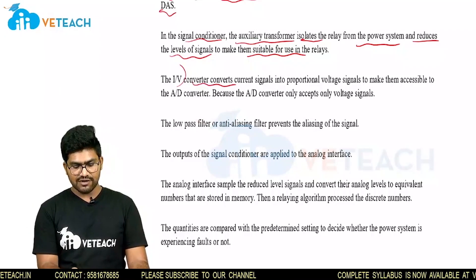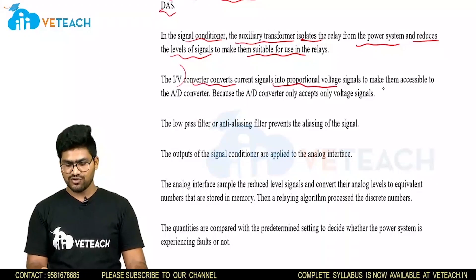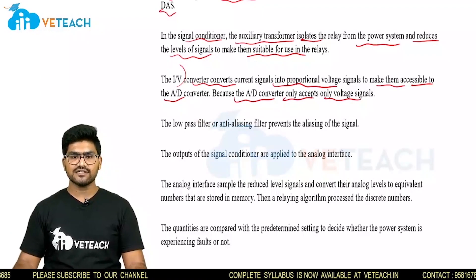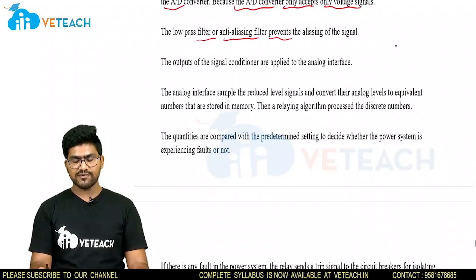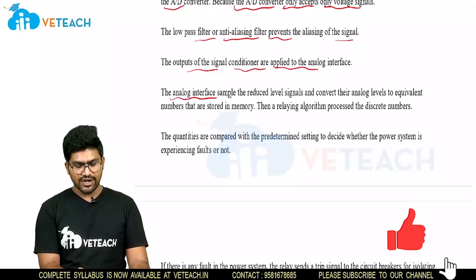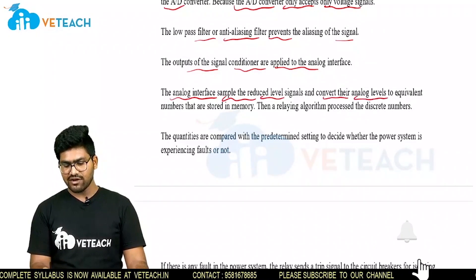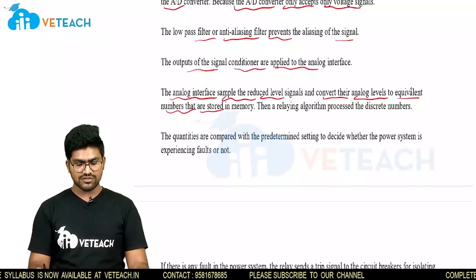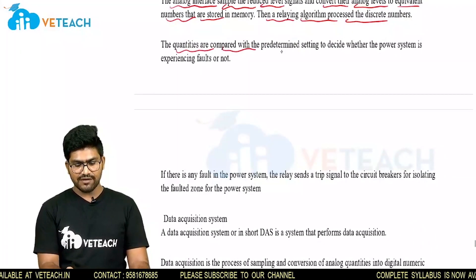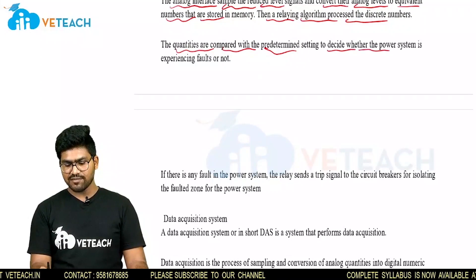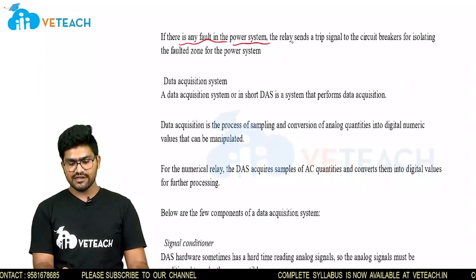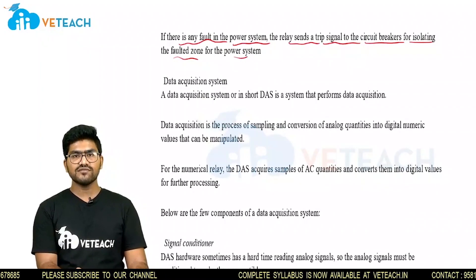The I to V converter converts current signals to proportional voltage signals to make them accessible to the A to D converter, because the A to D converter only accepts voltage signals. The low pass filter or anti-aliasing filter prevents the aliasing of signals. The outputs of the signal conditioner are applied to the analog interface. The analog interface samples the reduced-level signals and converts the analog levels to equivalent numbers that are stored in memory. A relaying algorithm then processes the discrete numbers. The quantities are compared with predetermined settings to decide whether the power system is experiencing faults or not. If there is any fault, the relay sends a trip signal to the circuit breaker to isolate the faulted zone.